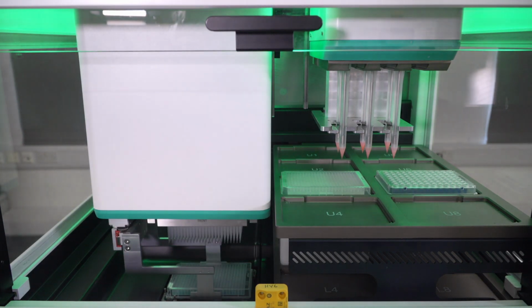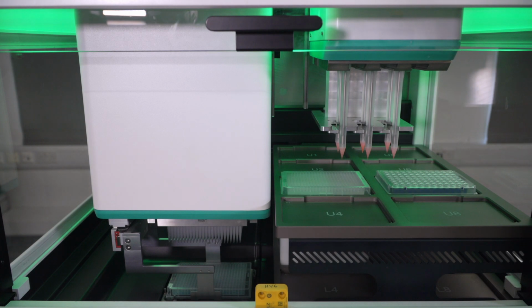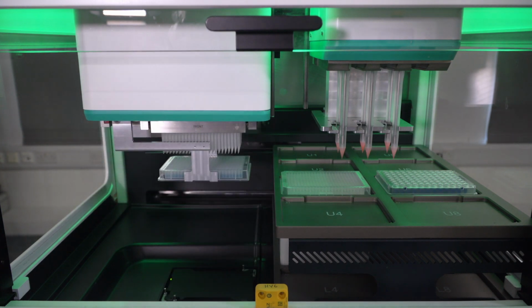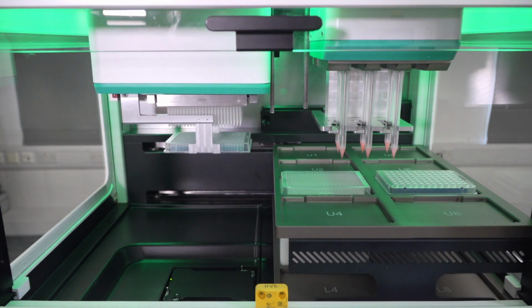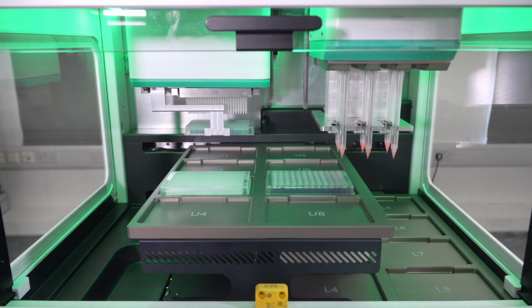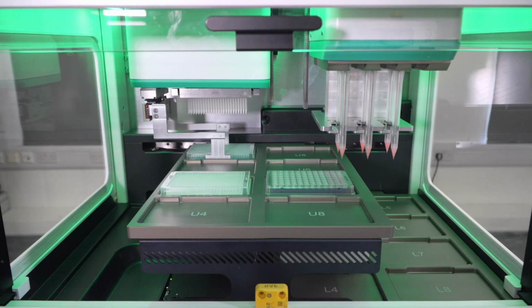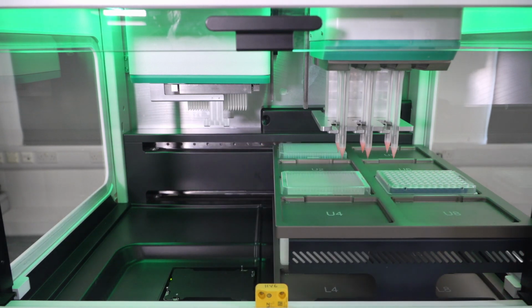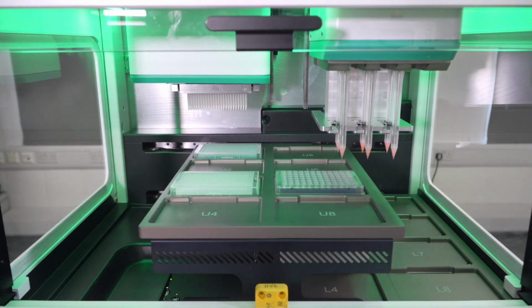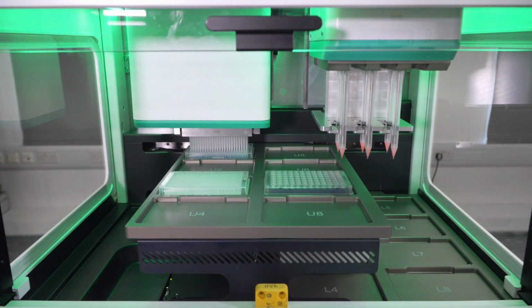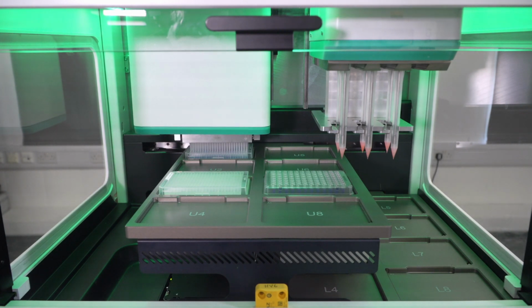So it's now just after a very short shake for this demo. We'd probably shake for longer in reality, but it's just doing a short shake, and now it's going to pick up the plate and bring it back to the deck for the final part of this short demonstration. And the next part is going to actually utilise the 384 tips, and it's now just going to take a copy of those samples in the 384 well plate and make a replicate plate in the other 384 well plate that's on the deck. So now it's going in, aspirating from that plate, taking a short air gap, and then it's moving in, aspirating, and then it's going to transfer that over to the final destination plate.